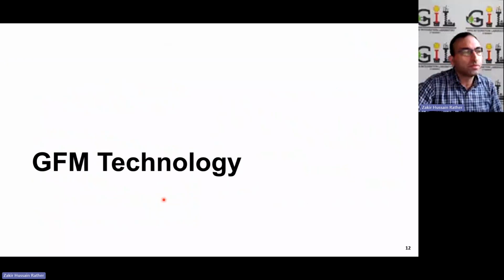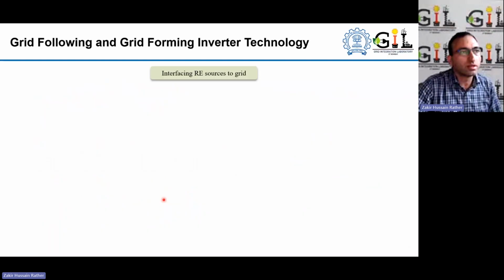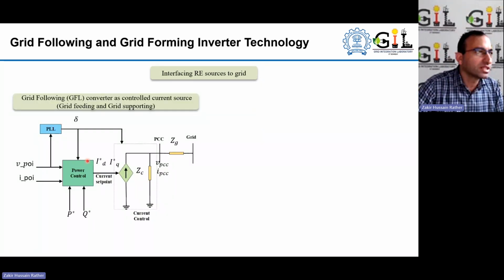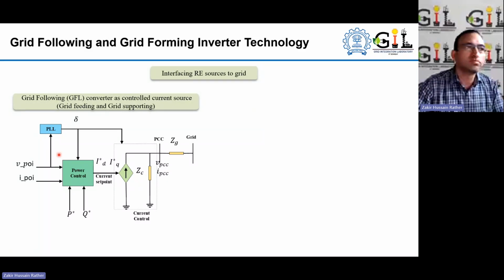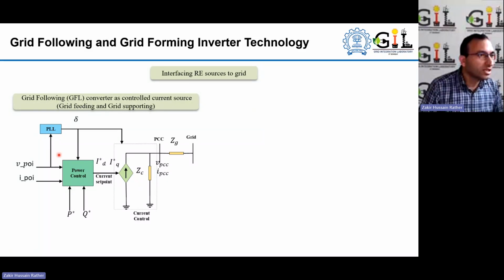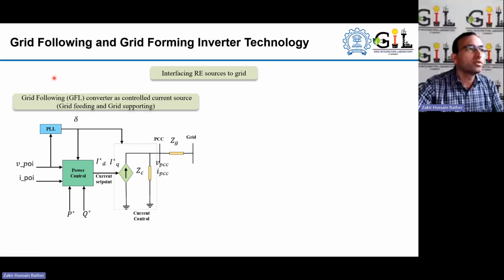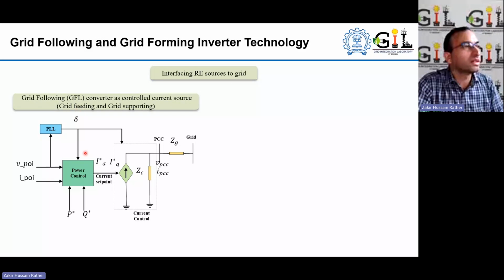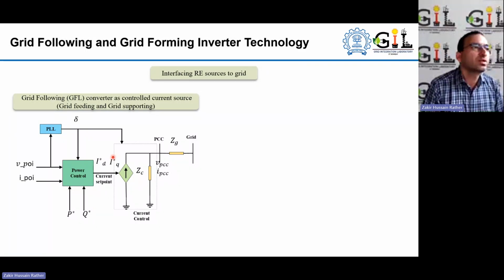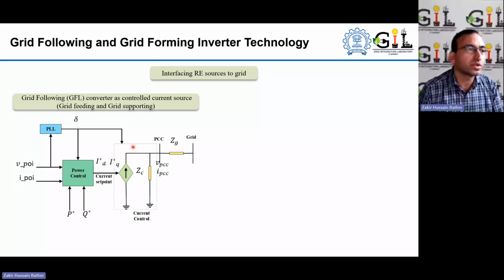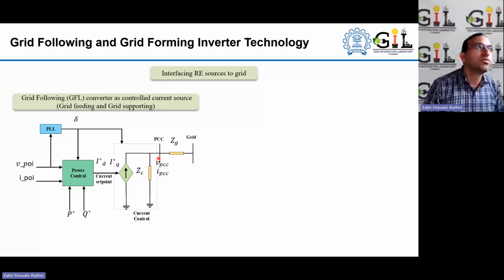Now, a little introduction about grid forming technology. As I mentioned earlier, we have been having grid following technology across the world, through which we have been introducing these renewables into the system. This grid following technology started primarily with what we call grid feeding technology, where the converter, to be precise the inverter, is injecting a controlled current from the IBR into the system, as you can see. So it has control over the current, but it does need the voltage and frequency.